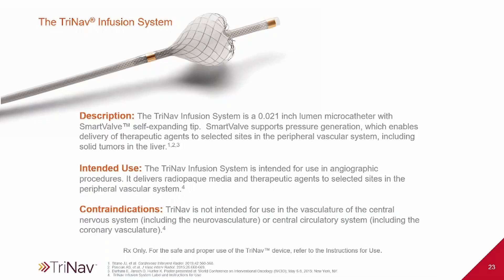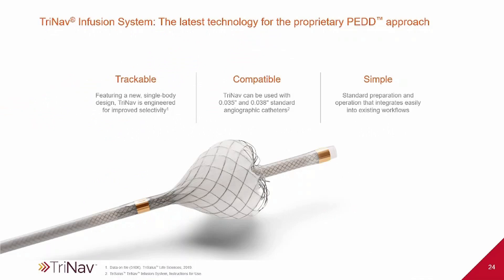Just real quick about the TriNav infusion system: it is a 0.021-inch lumen microcatheter with a SmartValve self-expanding tip. The SmartValve supports pressure generation, which enables delivery of therapeutic agents to selected sites in the peripheral vascular system, including solid tumors in the liver. Now, the one thing this is not intended for — contraindications — TriNav is not intended for use in the central nervous system, including neurovasculature or central circulatory systems, including coronary vasculature. So, not for the heart. This right here is a close-up of the catheter tip; it is compatible with 0.035 and 0.038 standard angiocatheters, but this right here is the smart tip.